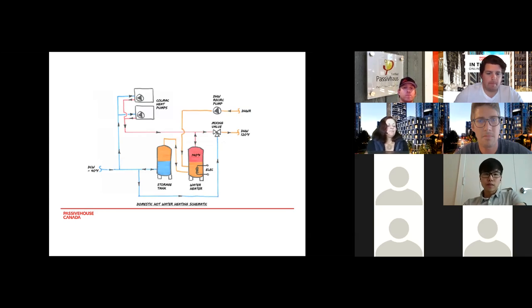I'm going to quickly touch on a simplified version of the domestic hot water schematic. There are 4 points I want to highlight. The first is the location of the equipment. I had 2 Colmac heat pumps on the roof, while the rest of the equipment—the storage tank, the electric water heater, the mixing valve, and the domestic hot water recirc pump—were located in a small mechanical closet on the floor directly below.